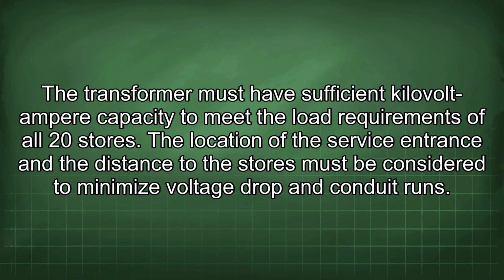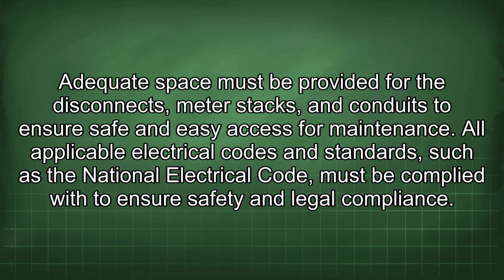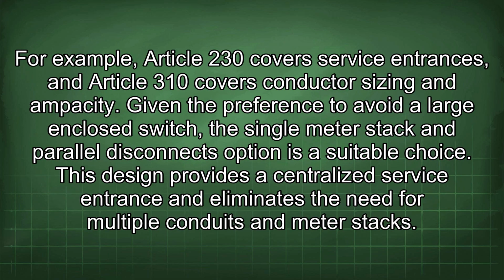The transformer must have sufficient kilovolt ampere capacity to meet the load requirements of all 20 stores. The location of the service entrance and the distance to the stores must be considered to minimize voltage drop and conduit runs. Adequate space must be provided for the disconnects, meter stacks, and conduits to ensure safe and easy access for maintenance. All applicable electrical codes and standards, such as the National Electrical Code, must be complied with to ensure safety and legal compliance. For example, Article 230 covers service entrances, and Article 310 covers conductor sizing and ampacity.